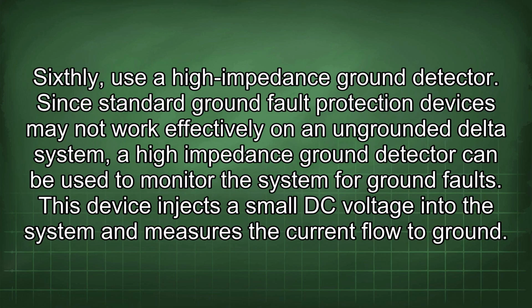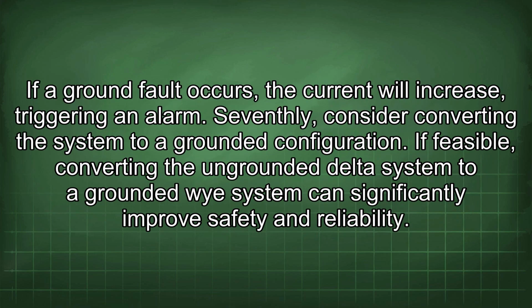Sixthly, use a high-impedance ground detector. Since standard ground fault protection devices may not work effectively on an ungrounded delta system, a high-impedance ground detector can be used to monitor the system for ground faults. This device injects a small DC voltage into the system and measures the current flow to ground. If a ground fault occurs, the current will increase, triggering an alarm.